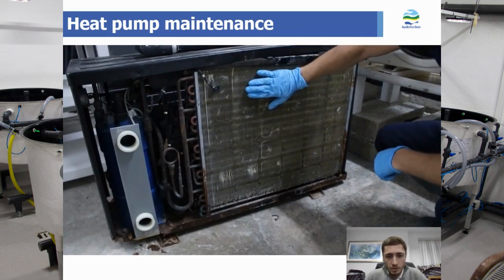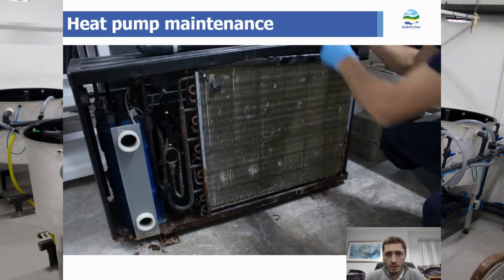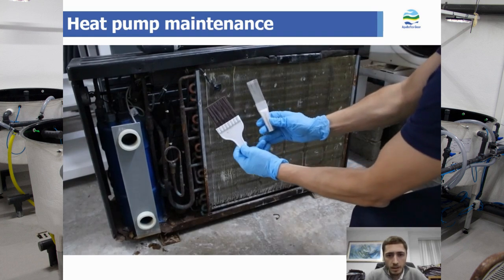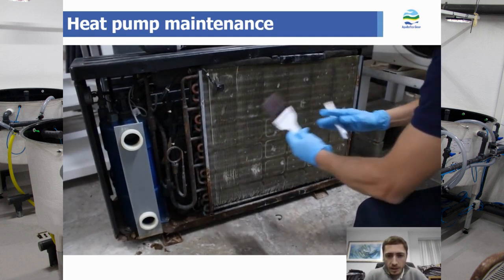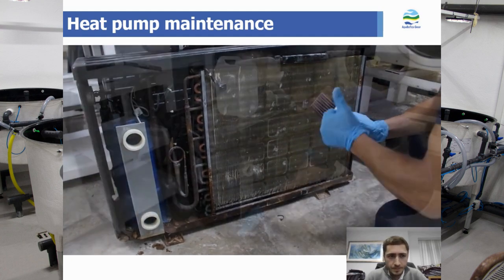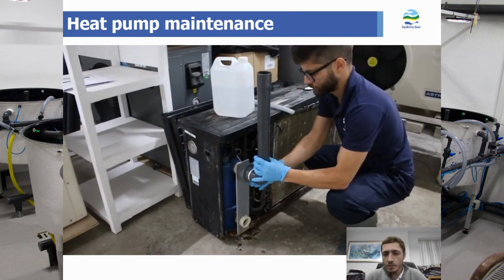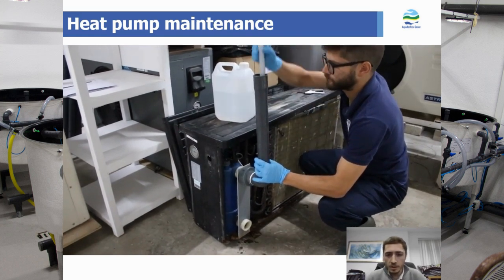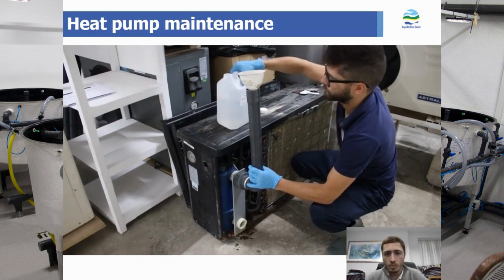So here are some of the internal components. On the left there is the main heat exchanger where water is coming in cold or hot and coming out hot or cold. And then on the right we have the radiator plate or the air-refrigerant exchanger. To clean this we use two brushes — one hard steel brush to separate the fins, because they can clump together over time, and then just brush away any dirt. You can see a good amount of dust coming off there. Again similar to the circulation pumps, for decalcification or clearing of the insides, you can use the submersible pump setup or just cover the bottom end and fill up from the top with your vinegar solution or bleach, whatever you need.